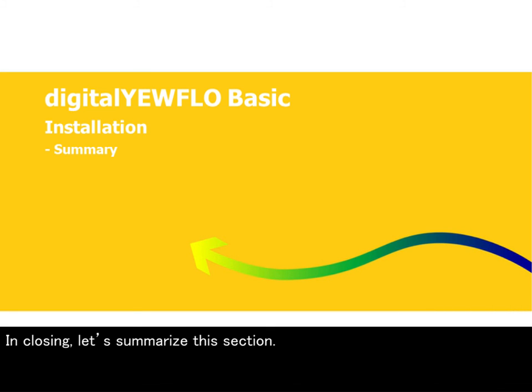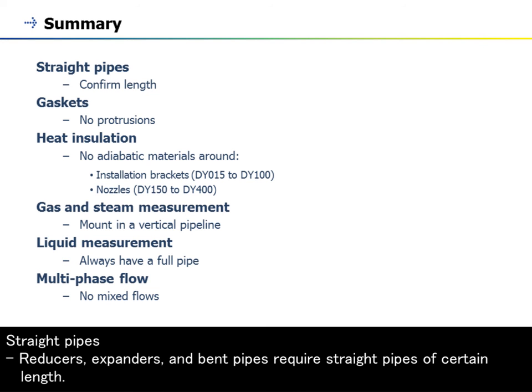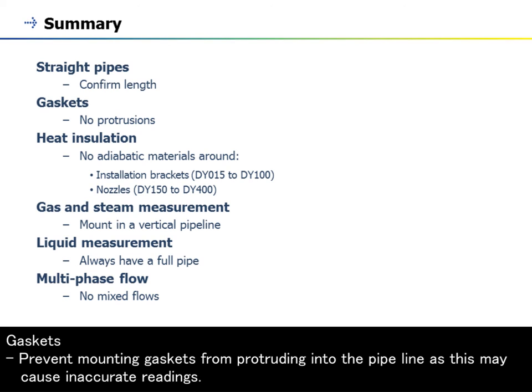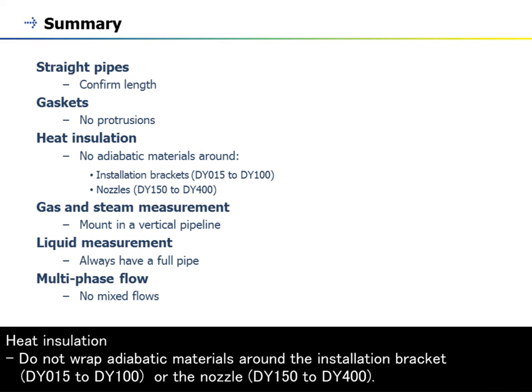In closing, let's summarize this section. Straight pipes: reducers, expanders, and bend pipes require straight pipes of certain length. Gaskets: prevent mounting gaskets from protruding into the pipeline as this may cause inaccurate readings. Heat insulation: do not wrap adiabatic materials around the installation bracket, DY-15 to DY-100, or the nozzle, DY-150 to DY-400.